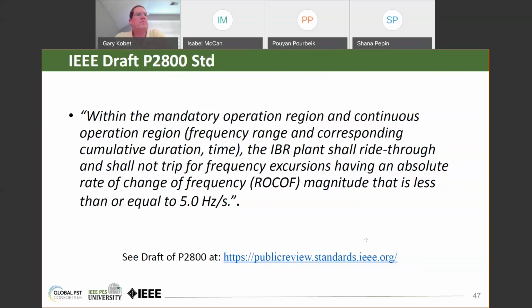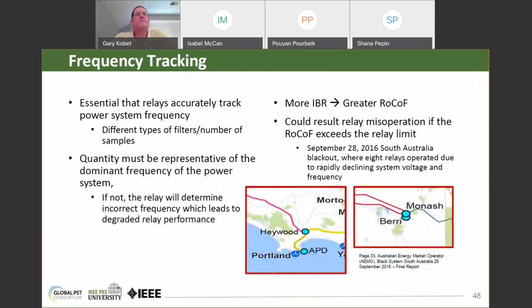Next slide. So frequency tracking is also something that can be affected here, where microprocessor relays are attempting to determine the system frequency. If the frequency is changing more rapidly, then you may lose frequency tracking, is the issue there. So that's another issue. Next slide.